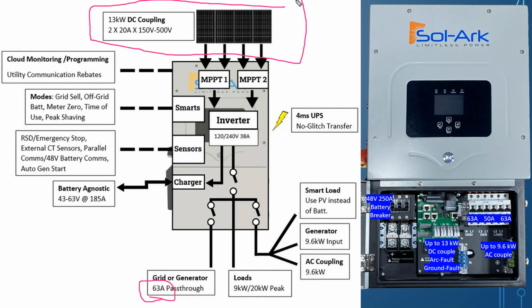Finally, in terms of a good solar size to combine with a Sol-Ark unit doing DC coupling, you can get up to 13 kW on solar. So when you're deciding how much solar to do, going all the way up to 13 kW per Sol-Ark unit is quite cost effective. When you look at the price of not having an all-in-one unit, but separating out the inverter from the charge controllers, the auto gen start, and the switch gear built into the Sol-Ark, it's so much more expensive than the all-in-one unit. Sol-Ark knows that, which is why it's so popular today.